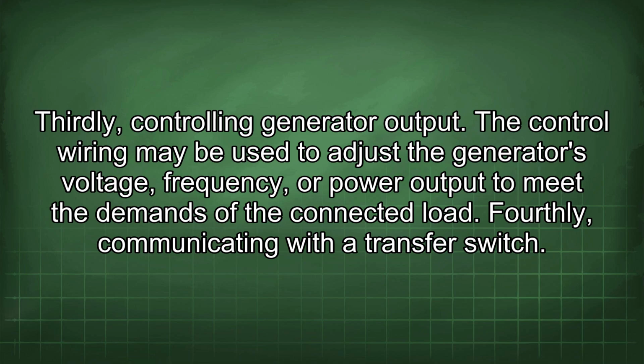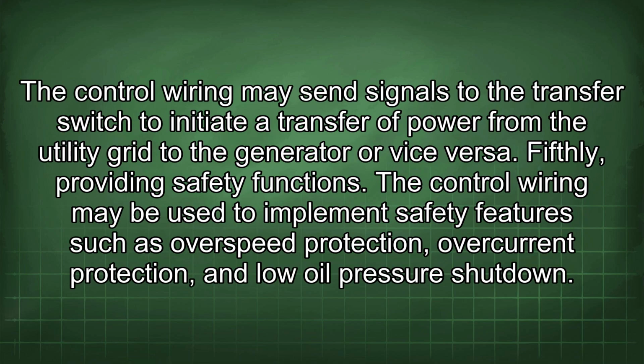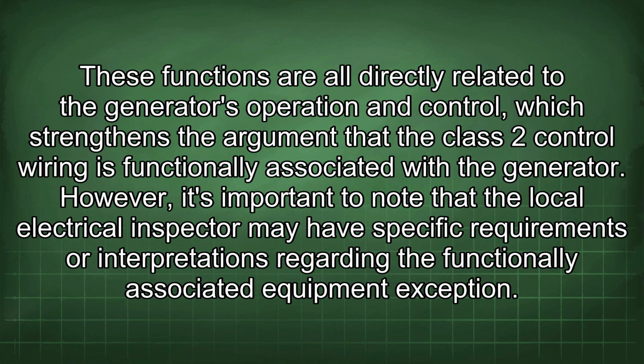Fourthly, communicating with a transfer switch. The control wiring may send signals to the transfer switch to initiate a transfer of power from the utility grid to the generator or vice versa. Fifthly, providing safety functions. The control wiring may be used to implement safety features such as overspeed protection, overcurrent protection, and low oil pressure shutdown. These functions are all directly related to the generator's operation and control, which strengthens the argument that the Class 2 control wiring is functionally associated with the generator.